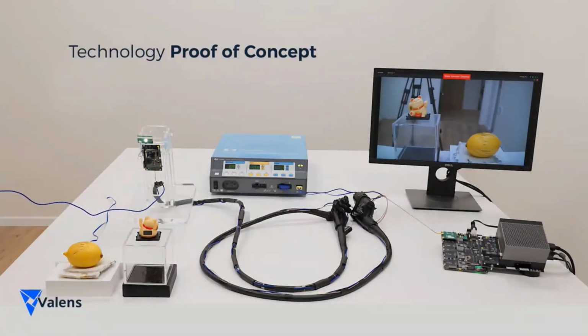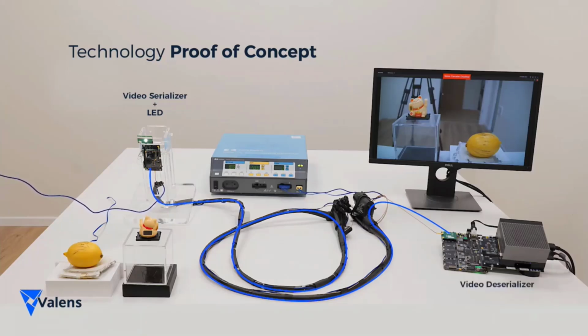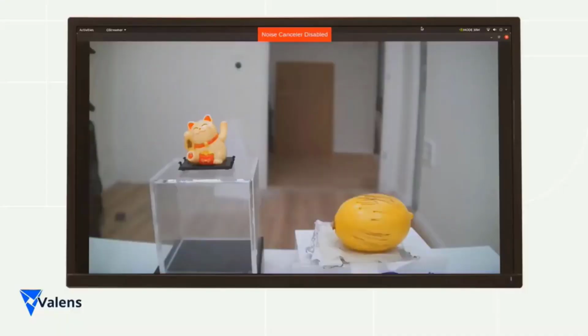The sensor data is driven from the tip of the scope using the Valens VA7031 serializer over a very thin and flexible 5-meter coax cable. On the receiving end, the Valens VA7044 deserializer is connected to the NVIDIA Orin processor that displays the 4K video. Solutions on the market today using only forward error correction or no correction methods at all cannot handle the electrosurgical procedure interference. We simulate this by running the setup with the VA7000 noise canceller disabled.